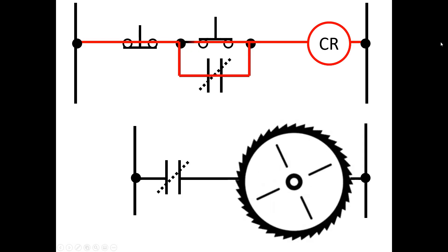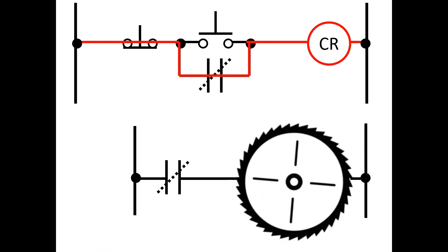The next step is I release my finger from the push button and the coil remains energized because the current for the coil is flowing through the closed contact, which is referred to as the holding contact.